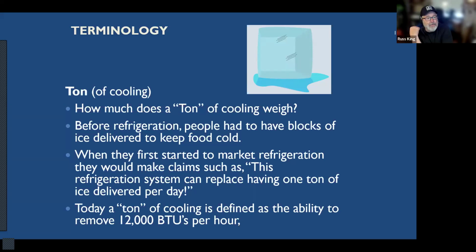Well, when they came out with mechanical refrigeration, the only way they could explain it to people was to say, "Oh, this piece of equipment will cool the same as 2 tons of ice or 3 tons of ice or 4 tons of ice," or something like that. And so that's where they came up with the term tons, all right? Well, the true definition of a ton has evolved to mean 12,000 BTUs per hour. Another way to think of that is 1 ton of ice can absorb 12,000 BTUs in an hour, and it will melt. Okay, so that's what the term ton means.